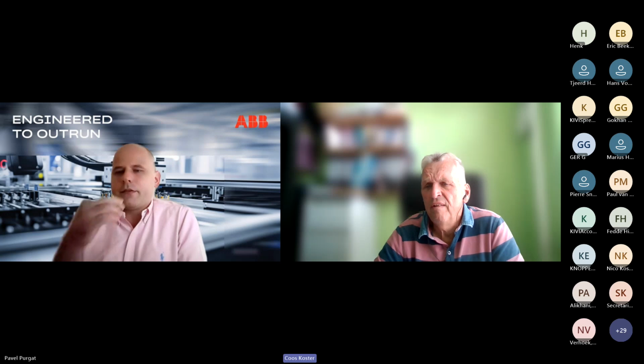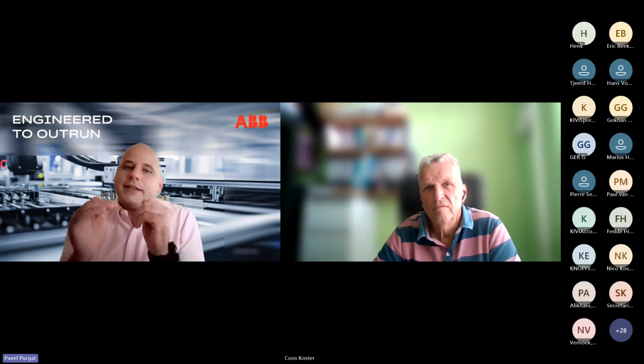Right. The next question is from Gerard Vromans. How do you know if the semiconductors can survive the short circuit generated from the grid or the source, or is the intent to replace the semiconductor? No. This is the cool thing about the semiconductors. They are so fast that the I²T doesn't have time to build up. We detect the fault very quickly, already at the lower magnitude of the current, and we switch within a few microseconds. So the I²T, compared to a fuse, is not 100 times smaller. It could easily be 10,000 times smaller depending on the rating. And this is the consequence of what I said. You define the let-through current, so you know what the let-through current through your semiconductor protection device will be. So as a matter of fact, you don't need to replace it. It can survive many short-circuit events. Yes, right, okay. It doesn't age.